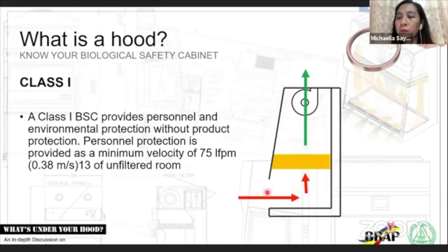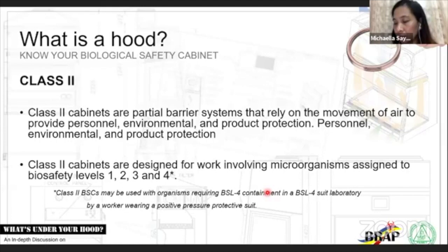Now, class 2. Class 2 cabinets are partial barrier systems that rely on movement of air to provide personal, environmental, and product protection. I need to emphasize that one: and product protection. Okay? Class 2 cabinets are designed for work involving microorganisms assigned to biosafety 1 up to 4. Again, this should not be used as a standalone biosafety measure. It should be used in tandem with different engineering, admin, work practices, and PPE. So you could use your class 2 for biosafety level 4. However, it must be located within a biosafety level 4 facility. Don't go to your boss and say, "Boss, meron tayong class 2A2. We could work with culturing COVID-19." Do not do that, right?